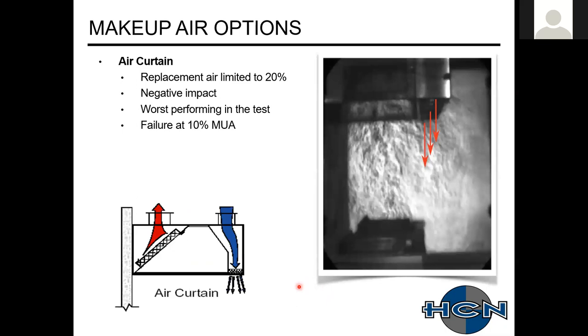Next one up after that is your air curtain. Typically, this actually performed the worst out of most of the systems, if I remember right. Your air just shoots down, and what typically happens is that air hugs that back wall and circles through. It doesn't always get pulled through the first stage, and it hits this cool air and then gets sucked out and pulled out into the space. I think the air study showed 20% for most of the stuff I've seen. You're looking at 10 to 15% for the most part. You can utilize this system, but like I said, you're only going to get 15% before it starts affecting the overall capture of the hood and affecting the overall building space.